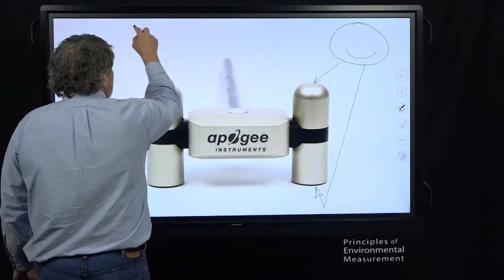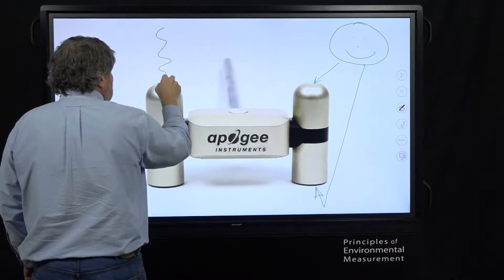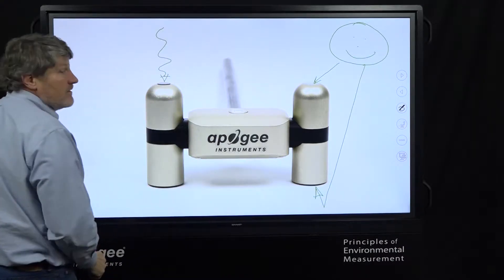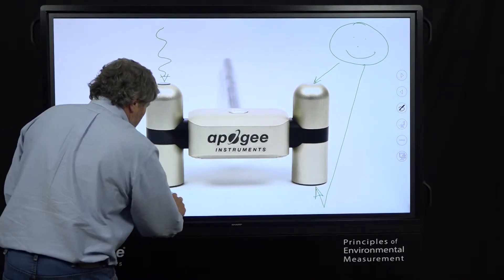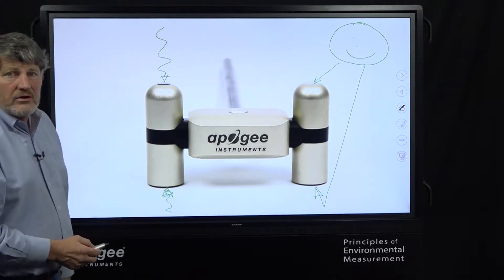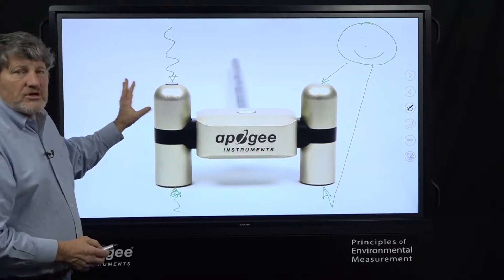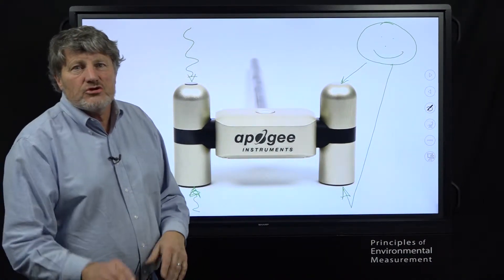Then we have longwave radiation from the sky coming in here measured here and longwave radiation from the soil here. That's a four component net radiometer, four separate measurements coming out to the instrument.